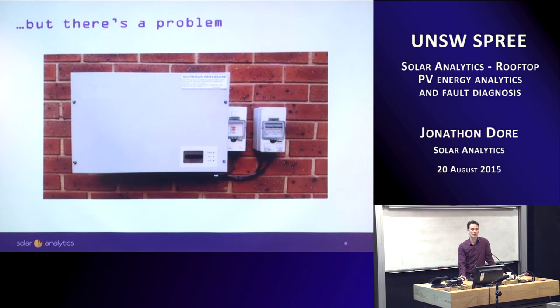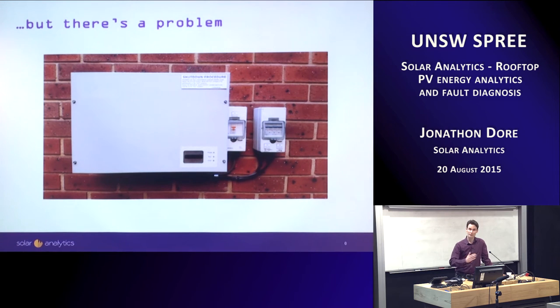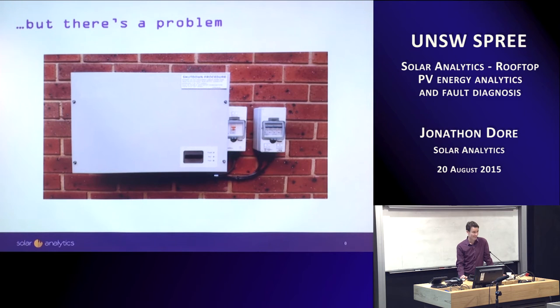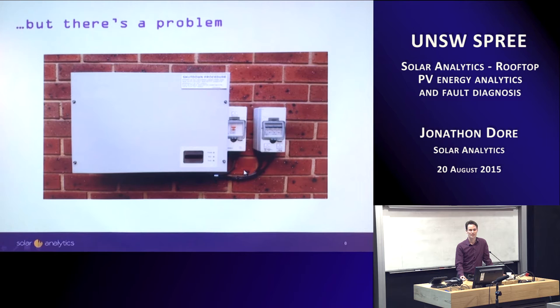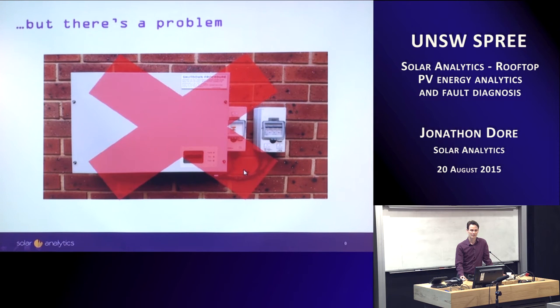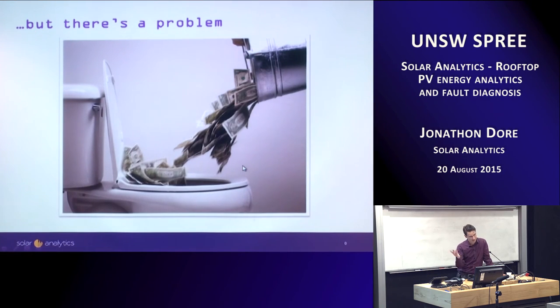Can someone guess what the failure rate of this inverter was per installation over their entire experience? Five percent? Higher. A hundred percent? Higher. A hundred and forty percent per installation. So many failed that some have been installed twice and both of them have failed. Although the panels we think are all fine, there are other issues around the installations.